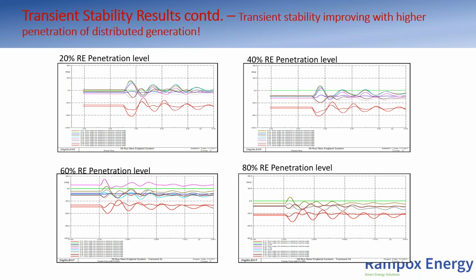So if the first swing is attenuating, it's a good sign that you are increasing your stability margins, which is what we're seeing here. You move from 40 to 60, and you see that they become smaller and smaller. Now they're even lower than the 20 that we saw at 40, and 80 is even lower. At 80 you see that it hardly gets to around 15, around 10, it doesn't even get there. So this attenuation of the first swing is showing you increasing stability. With the distributed renewable energy, you are seeing positive effects on the transient stability.